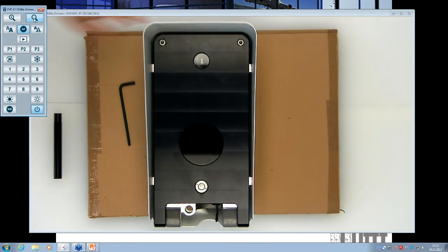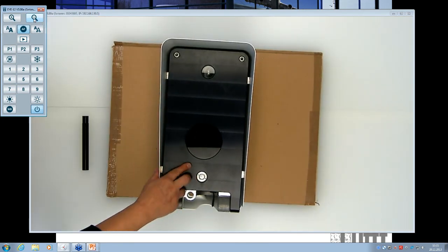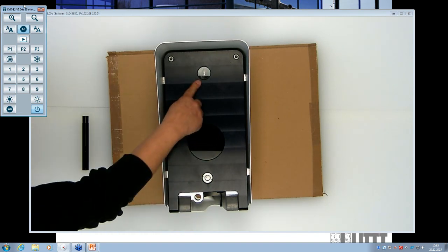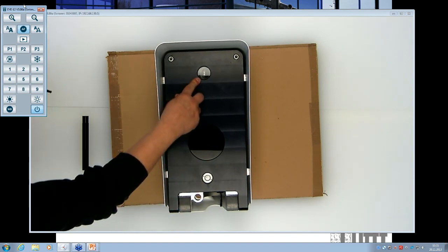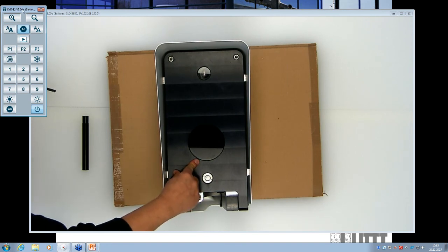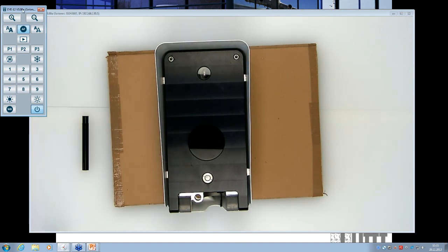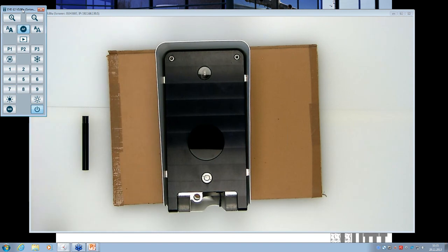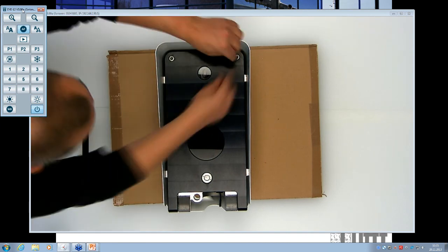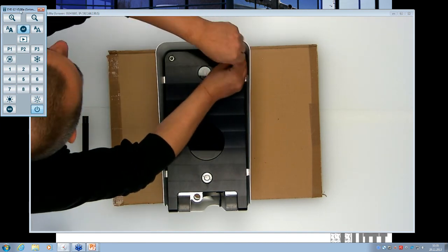So, of course, here are the plates which you should clean. These are the filter plate and the light source plate. You can use a cloth which is a little bit humid, and that's nothing special. Don't use any cleaner or something like that. Only clean it with a cloth which is a little bit damp, and that's okay. So now you can open the unit to change the reflector. I will show you how to do that. So you use your wrench here and open the screws.